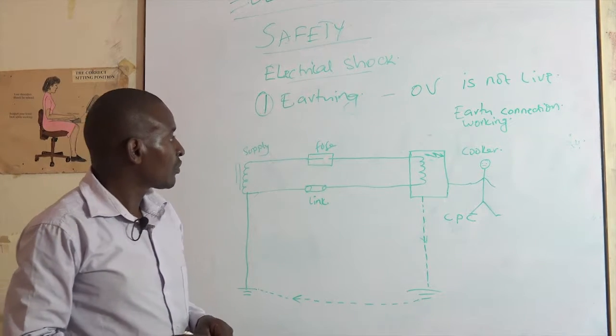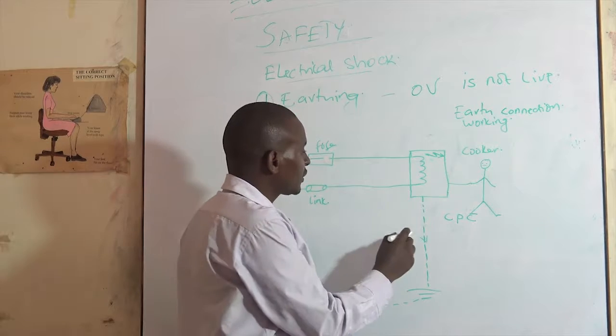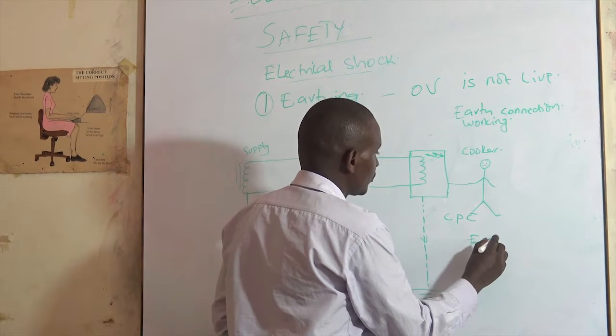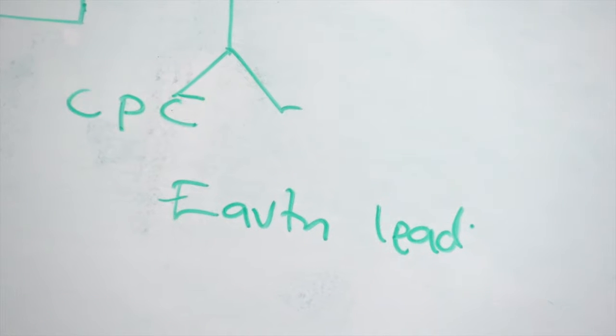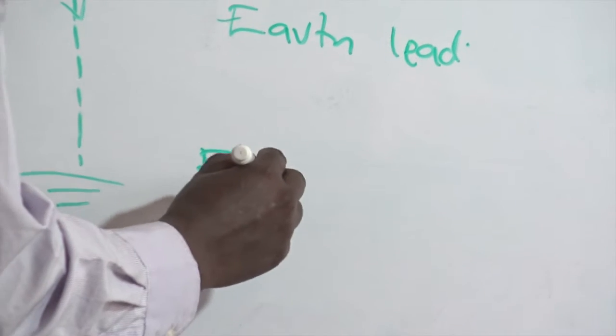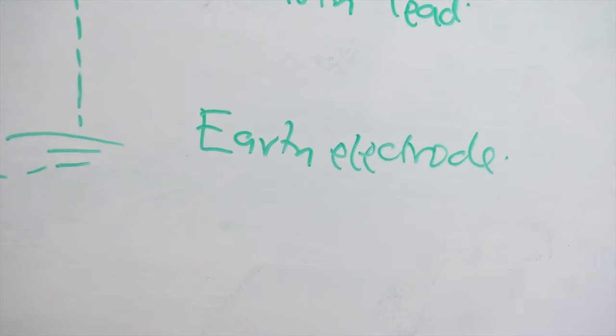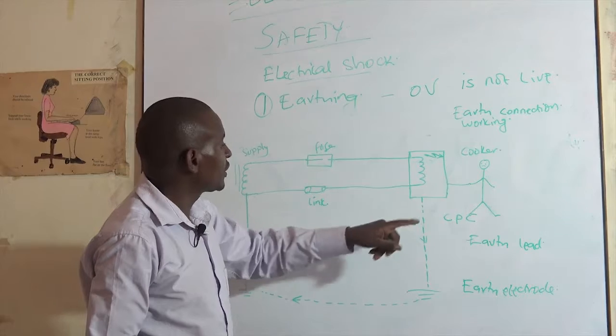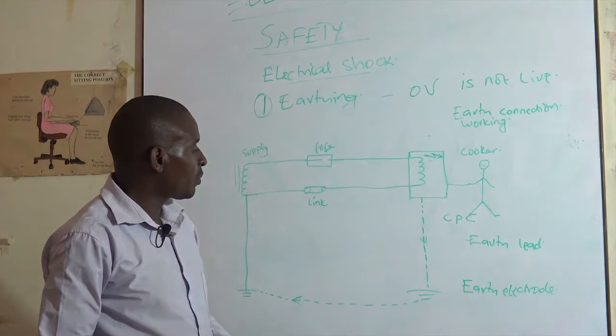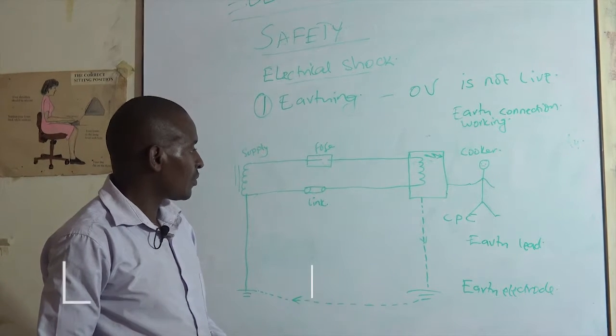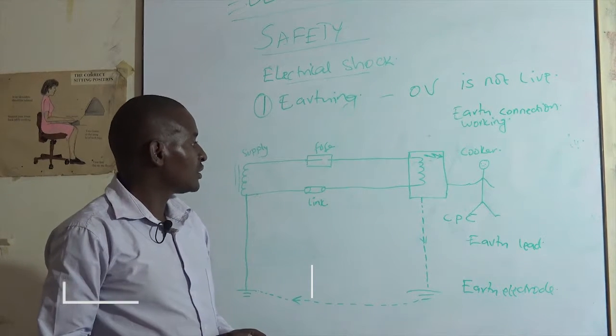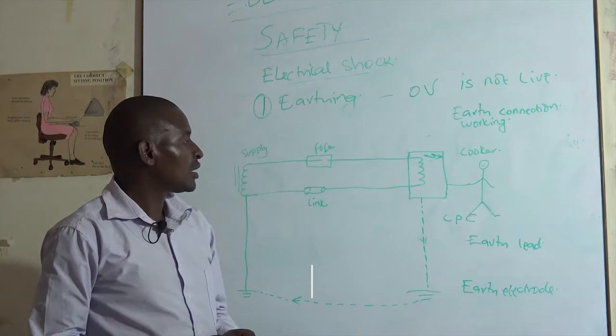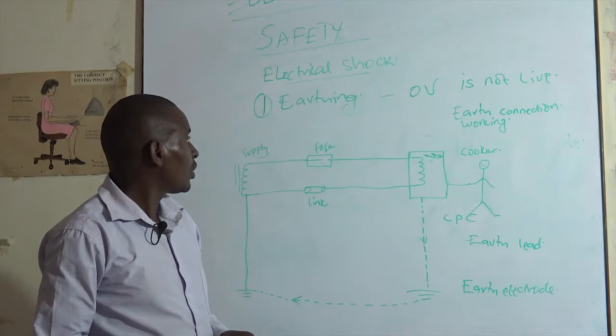So the other thing should be, other than a working connection, ensure that the earth lead is okay, and also ensure that the earth electrode is properly connected to the earth lead, and the earth lead is connected to the CPC, and then you have a very proper system that is safe. So that is what, as consumers of electrical energy, we should ensure before operating electrical equipment. That's what should be ensured.